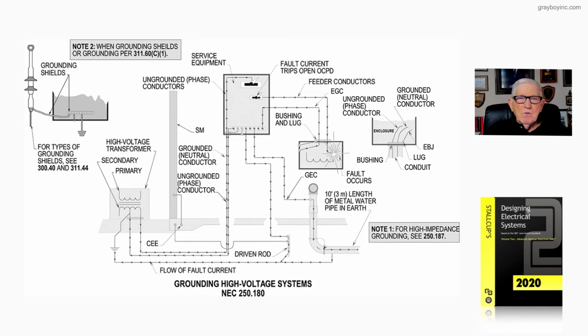And you know, we have some rule of thumbs that we use for that if you wanted to get into volume 1 of Stallcup's electrical design book that gives you some tips. And of course, any metal raceway has to have a bonding jumper, equipment bonding jumper, as you see in the illustration to your right there.